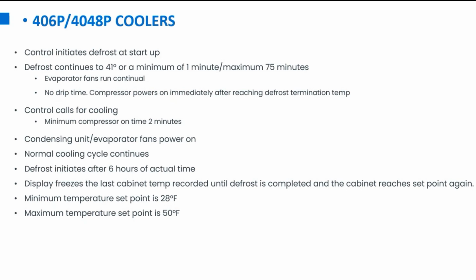The defrost on this will go through a defrost every 6 hours of actual time. So it's not based off of compressor runtime or evaporator coil temperature. It's strictly based off clock time. So the example I always use is if the unit goes into a defrost around 12 noon, it's typically going to go into a defrost again after about 6 hours of actual time. So it'll go in defrost again about 6 p.m. that night.